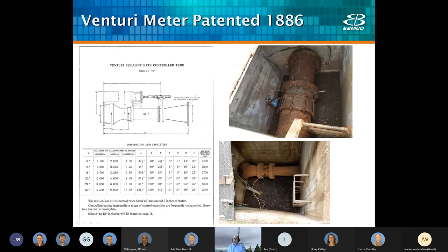The Venturi meter was primarily used for large plants and very large customer meters due to its low head loss and essentially maintenance-free operation. It is not as useful at low flows or for smaller meters. East Bay MUD also utilized short-body versions of these Venturis for compact operations. However, the Venturi has been found to have some limitations and possible errors, especially with short-body meters, so East Bay MUD has lately been replacing those with mag meters.